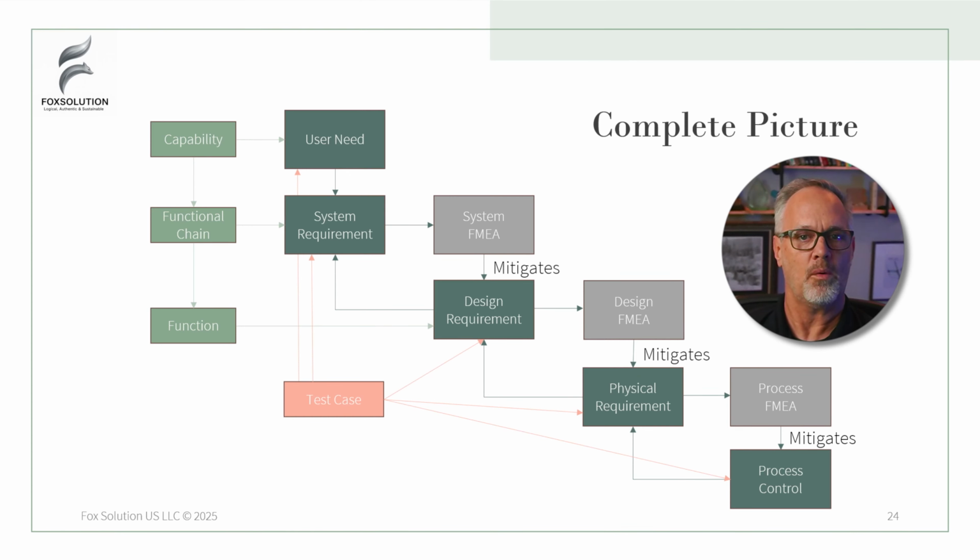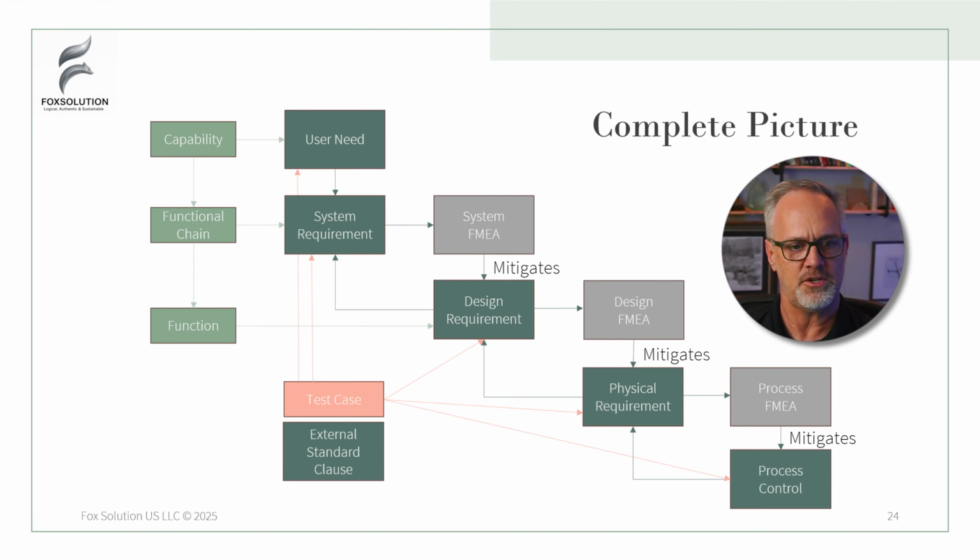So how are we going to assure that these are met? What test are we going to run? What's the procedure for the test? We have traceability to those external standard clauses. So we have an industry view of everything that's needed for the different scope issues inside of development of the project, whether it's 60601 or sterilization procedures or device specific stuff, testing procedures. All of the industry understanding has been baked into the requirements model. And then finally, we have this traceability to outputs.